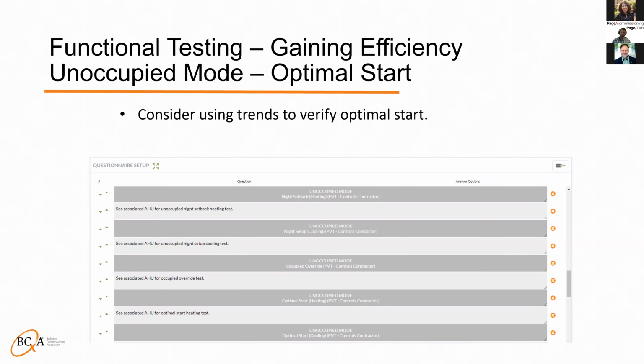So let's say your night setback set point is 55 degrees and you want to override your space temps to 56 degrees. This should force the morning warm up to start almost immediately. Then just verify the outside air damper remains closed and the associated exhaust remains off. As a quick note, most of the time optimal start is not spelled out in the sequence of operation. Either the engineer leaves it off the sequence completely, so you'll have to reference ASHRAE or IECC to get it programmed, or they just say provide optimal start without saying how it should be programmed.